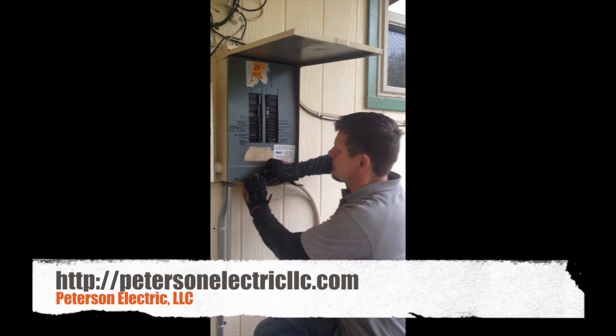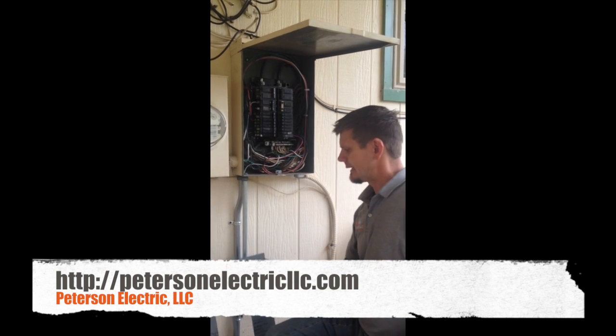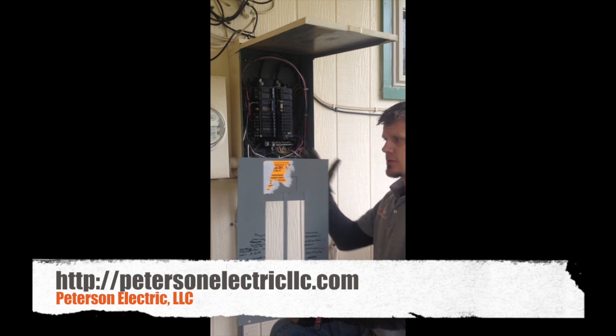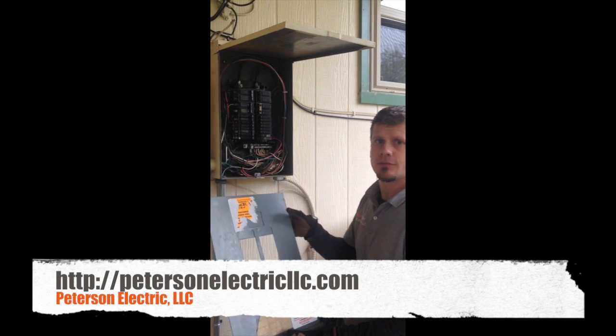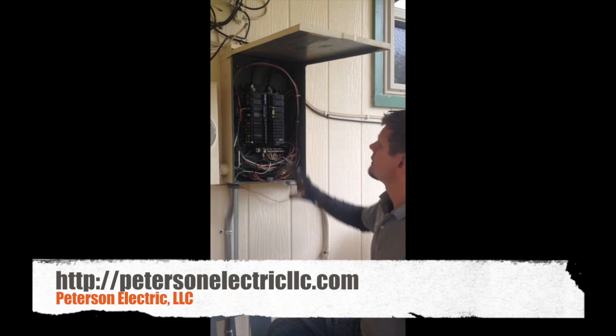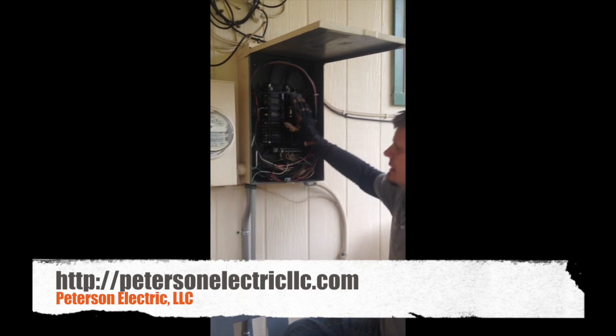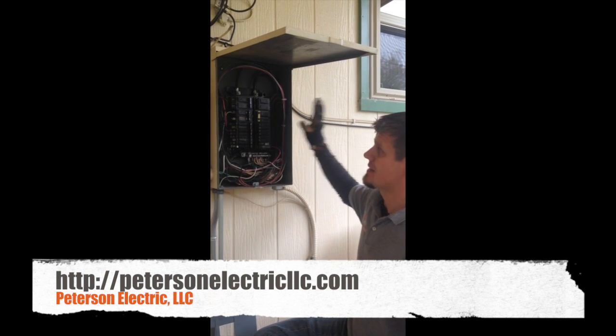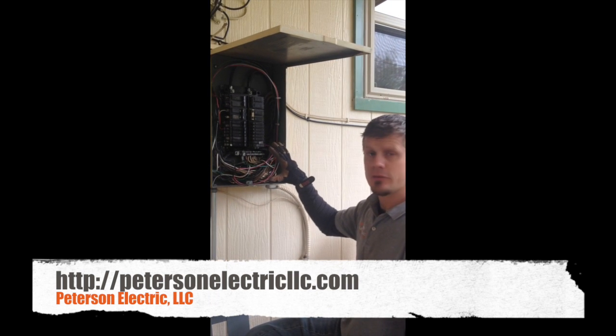I've been doing this about 17 years and it's been one of the hardest things to detect. I do not suggest you take this off — it's called a dead front cover, it's for a purpose. You'll get killed if you don't have it on the front. So when you take this off and you have your gloves on, you want to determine if you hear any sizzling. How I do that is I turn everything on in the home and compress that load to go right back to this panel.